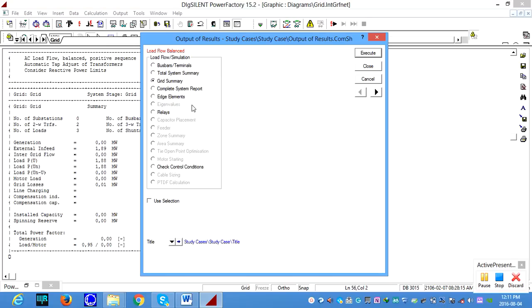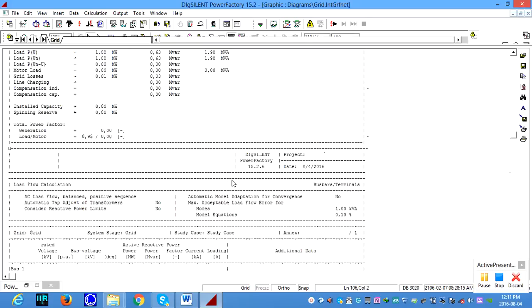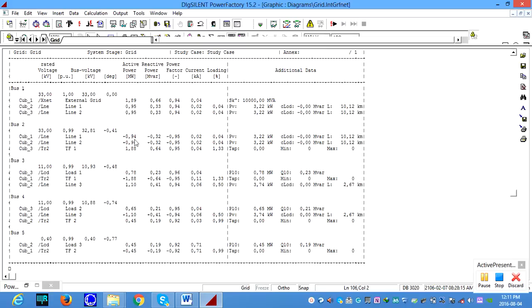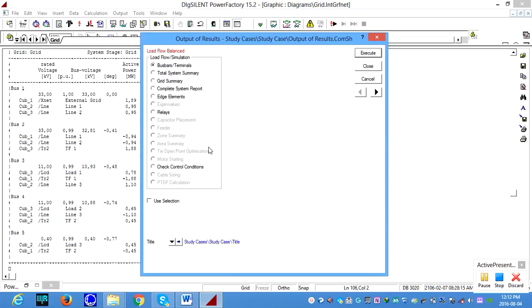To further validate the results, we can also check the bus terminals. Okay, and you can see for each bus terminal, you have bus 1 with 3 cubicles, bus 2 with 3 cubicles, 3, 4, and bus 5 with 2 cubicles. And you can see the active power and the reactive power, and also the power factor of the lines. And this is also additional data which is able to give you the apparent power, the copper losses, etc., on the specific bus with the cubicles. And to further analyze, you can also go to see the edge elements results.